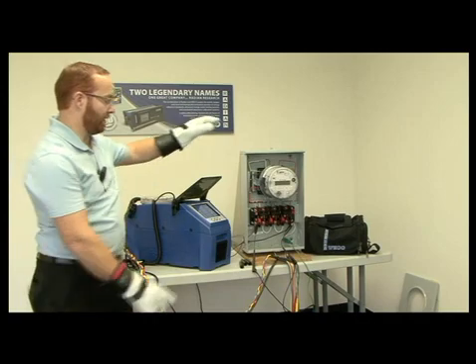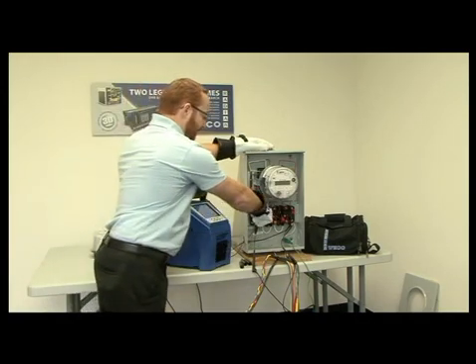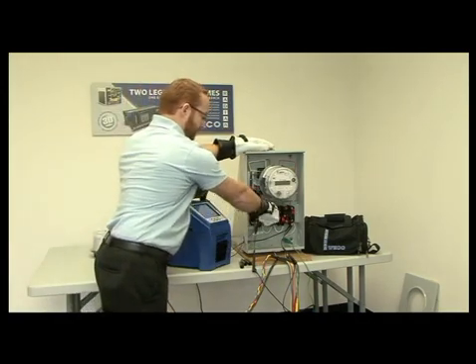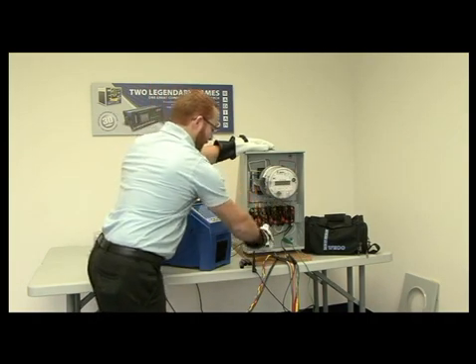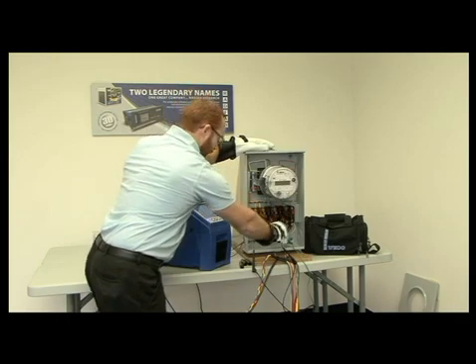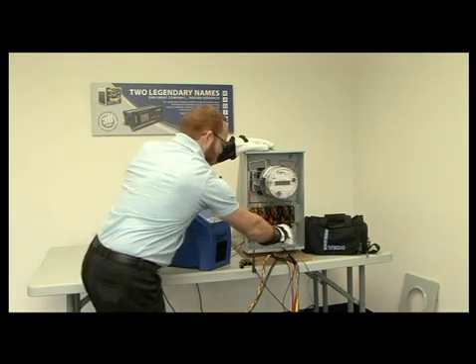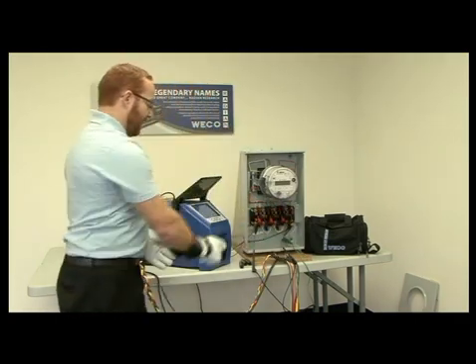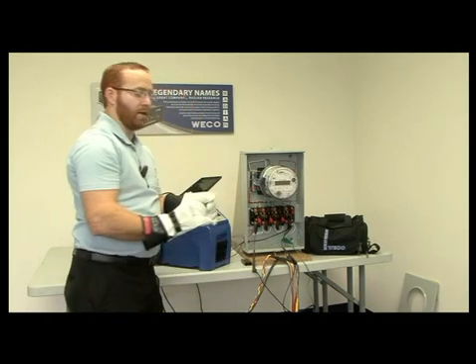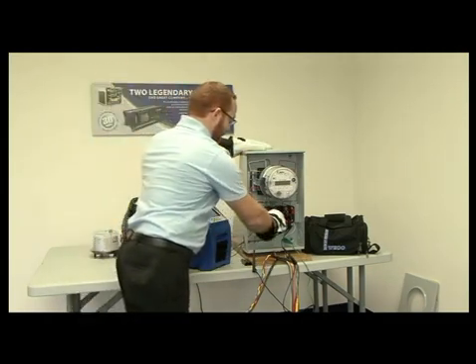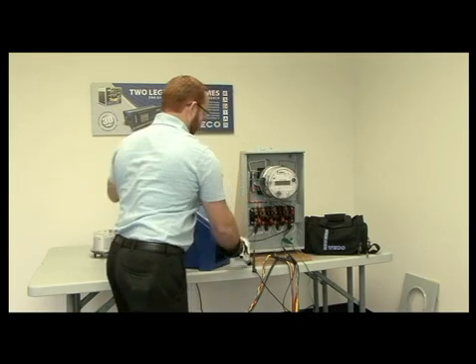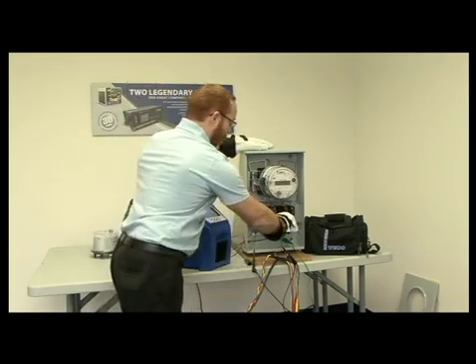Then I'm going to put the meter in bypass mode for the CTs. I'm going to remove the safety bypass because I would like to isolate the meter from the service. Next, I'm going to use my isolation plugs to isolate the meter from the CT service. I'm going to do this for all three phases.